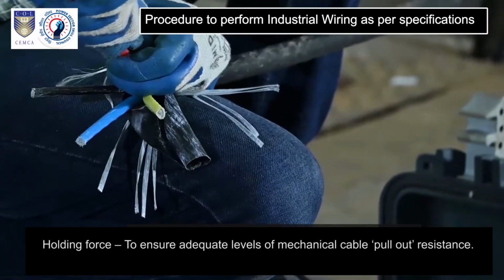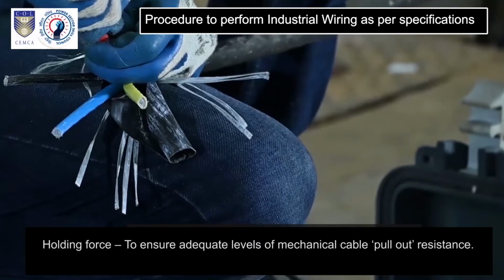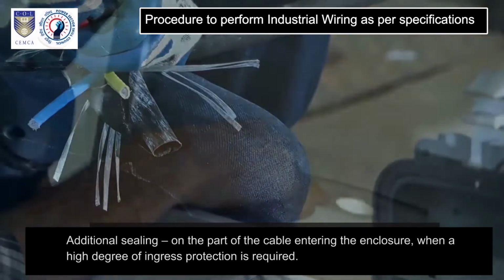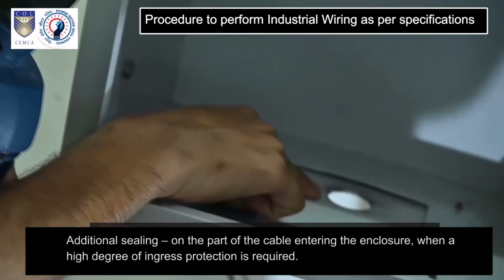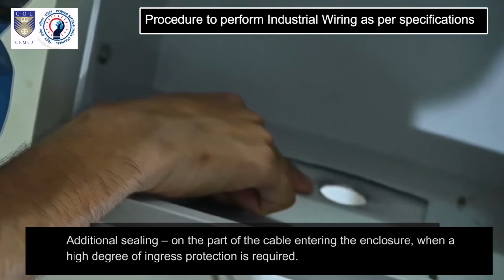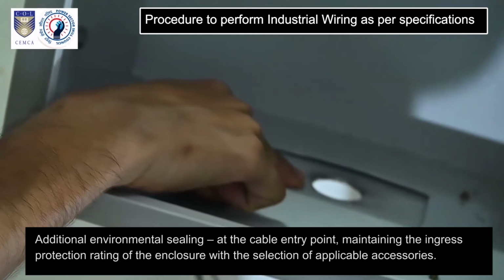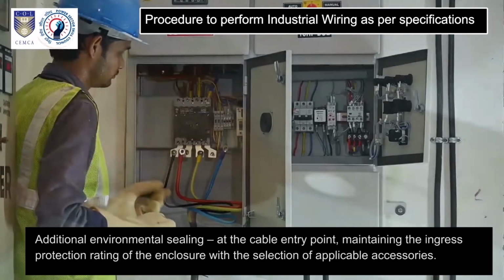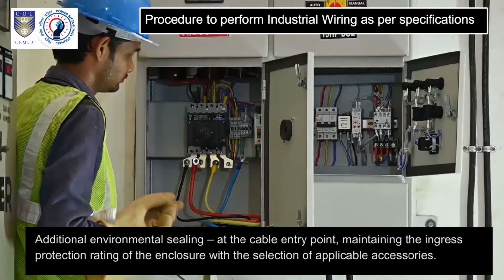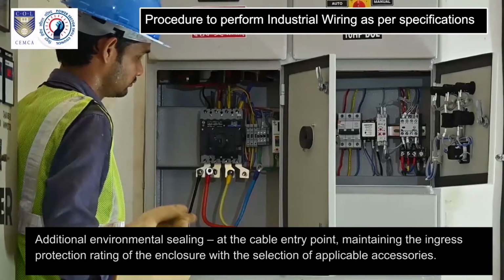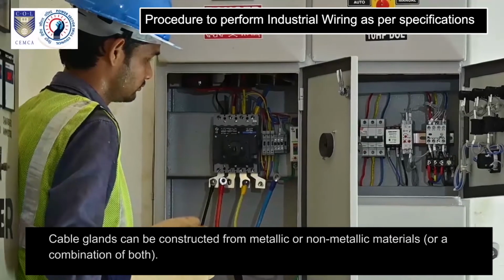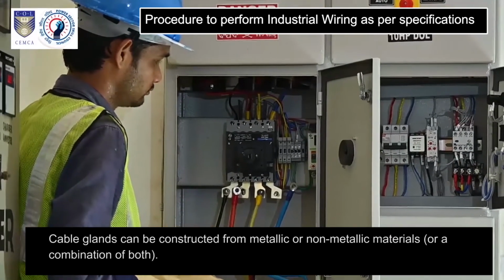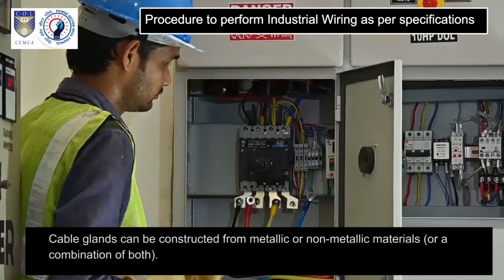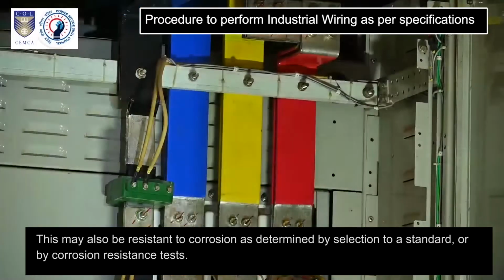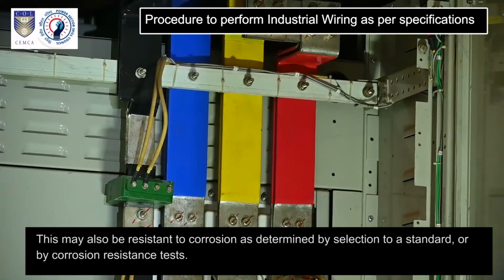Holding force, to ensure adequate levels of mechanical cable pullout resistance. Additional sealing, on the part of the cable entering the enclosure when a high degree of ingress protection is required. Additional environmental sealing, at the cable entry point, maintaining the ingress protection rating of the enclosure with a selection of applicable accessories. Cable glands can be constructed from metallic or non-metallic materials or a combination of both. This may also be resistant to corrosion as determined by selection to a standard or by corrosion resistance tests.